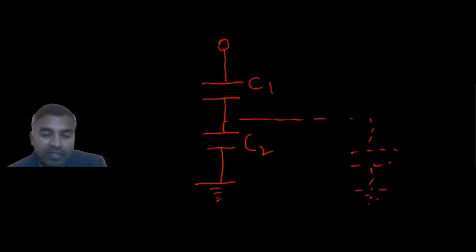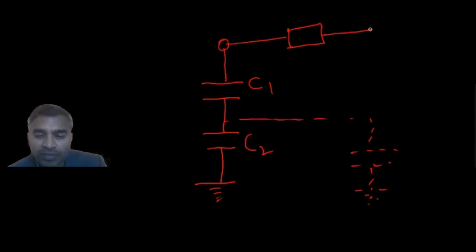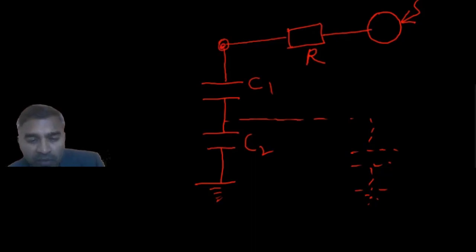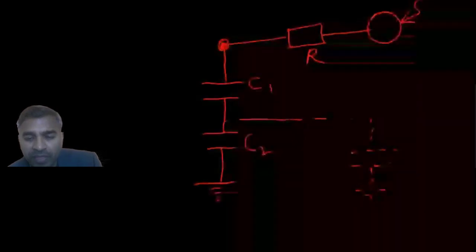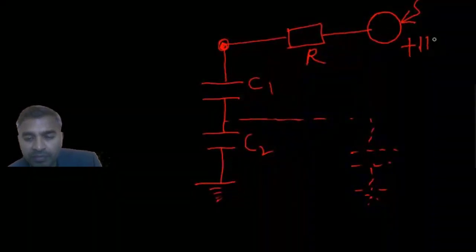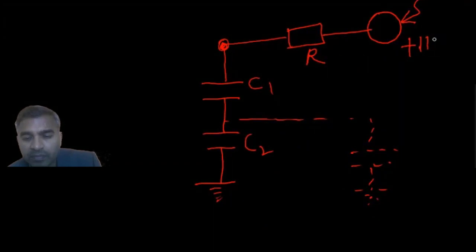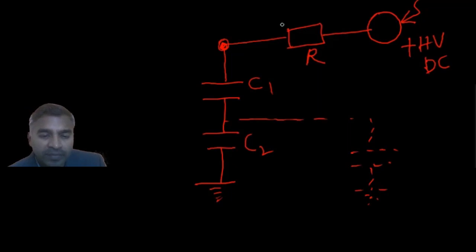So when you are connecting this, caution should be taken that it is connected to HV through a resistor of adequate resistance, so that there is a certain time constant to reach the maximum when you are connecting it to DC. Are you getting?